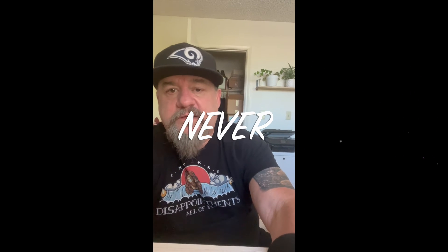He might be reading off another box. There might be things in the wall like other conductors — it's just shallow. You can read outside; you don't even have to be touching some things if the power's on. You can read it through a wall. It's not that the wall's hot; it's just reading what is hot. He's more or less reading something inside the wall, like a cable. Maybe the feeder cables are going through there — you've got 240 volt, you never can tell. But it's not like the house is hot. In this instance, never trust the tick tracer. That's the problem.